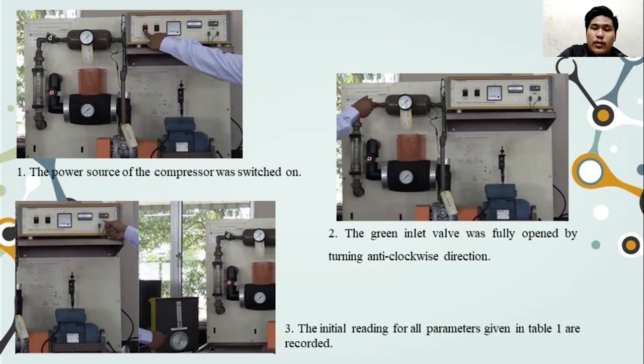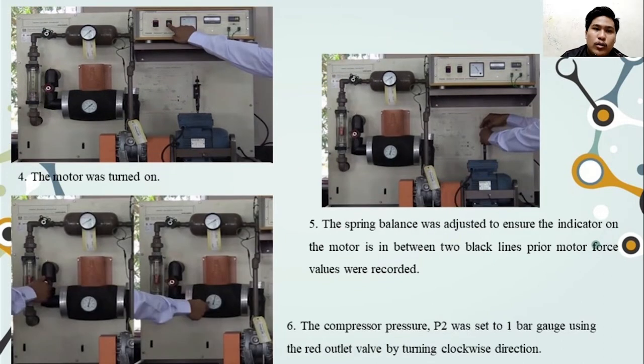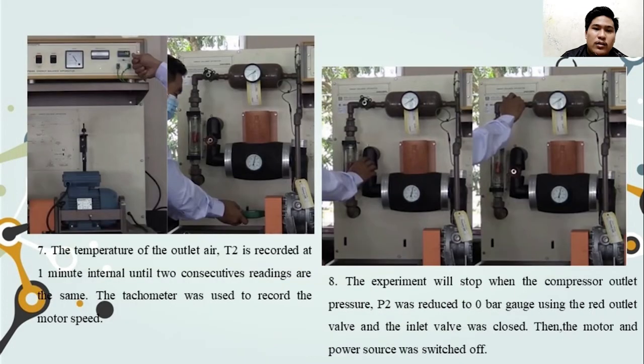My name is Baha bin Shaoli and I will present the methodology and conclusion. For the methodology: step one, the power source of the compressor was switched on. Step two, the green inlet valve was fully opened by turning anti-clockwise. Step three, the initial readings of all parameters in Table 1 were recorded. Step four, the motor was turned on. Step five, the spring balance was adjusted to ensure the indicator on the motor is between two black lines, and prior motor force values were recorded. Step six, the compressor pressure P2 was set to one bar gauge using the red outlet valve by turning clockwise. Step seven, the temperature of the outlet air T2 was recorded at one-minute intervals until two consecutive readings are the same.